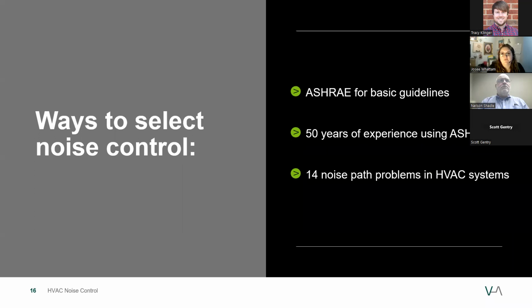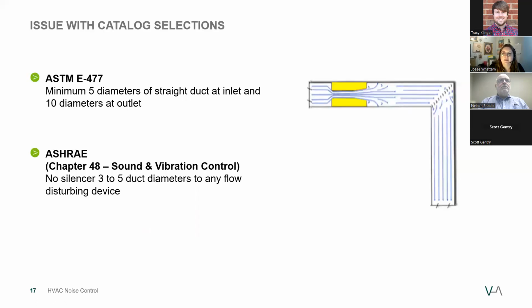In Vibro-Acoustics' 50 years of experience using ASHRAE guidelines, we have identified 14 common noise path problems in HVAC systems. I'm going to go over those in my RTU example later. But I want to talk about these guidelines that are used in creating the catalogs and selection softwares for noise control products. So there's ASTM E477 and ASHRAE. So both of those are guidelines that determine how much room is needed for a silencer to operate as published. ASTM recommends 5 duct diameters of straight ductwork at a silencer's inlet and 10 at the silencer's outlet. ASHRAE recommends keeping the silencer 3 to 5 duct diameters from any flow disturbing device, such as fans, elbows, plenums, or fittings.